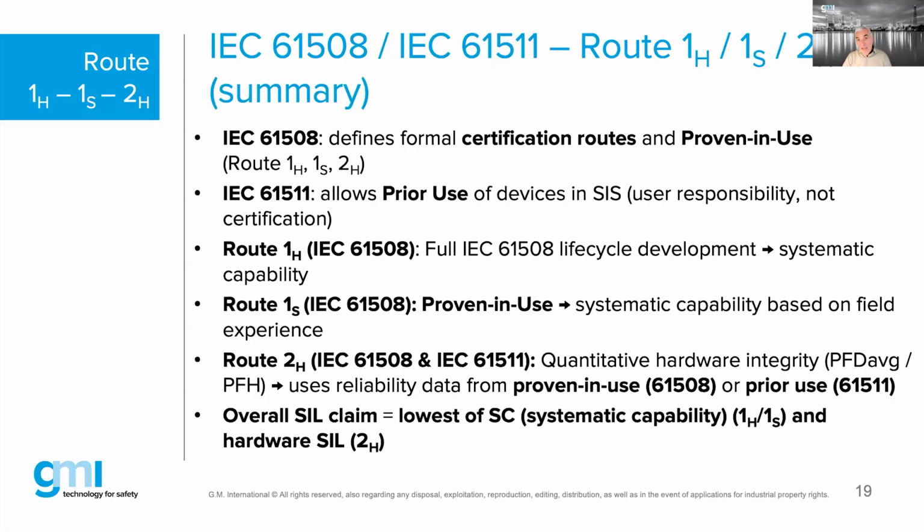Besides this Route 1H, which is the hardware approach, and the Route 2H, which was this proven or prior use approach, there is a fourth one, which I'm introducing here new in this webinar, because this webinar is repeated from a couple of years ago, and at that time, I did mention also Route 1H. Today, or in 2026, I see more and more evidence in literature, data sheets, certificates, reports, vendor data, that vendors are starting to mix proven in use, partially, but also Route 1S.